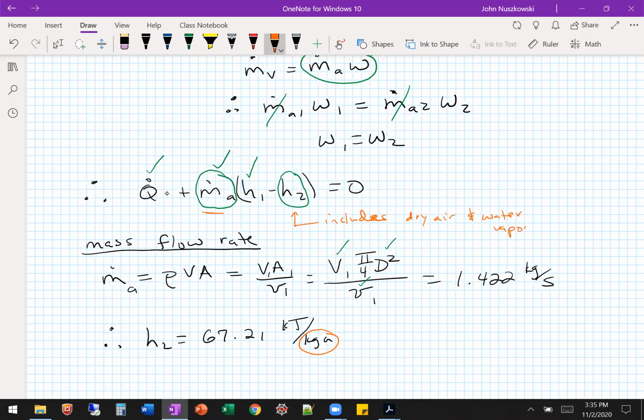We derived that in the lecture. Even though it's per kilogram of dry air, the kilojoules include the water vapor. So there's no Cp delta T we can put there, because the enthalpy includes the dry air portion, which is Cp delta T, but also the latent energy from the water. Even on the psychrometric chart, it includes that. So we have H2.